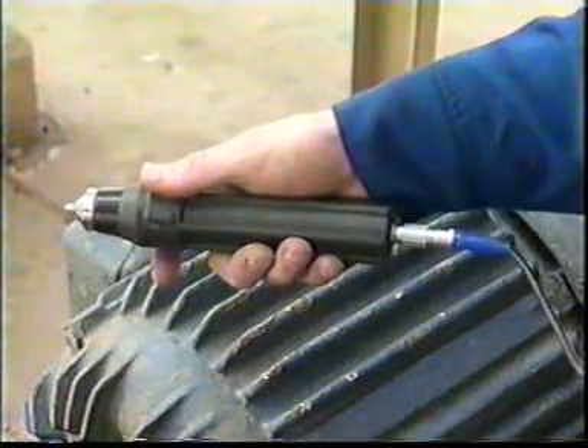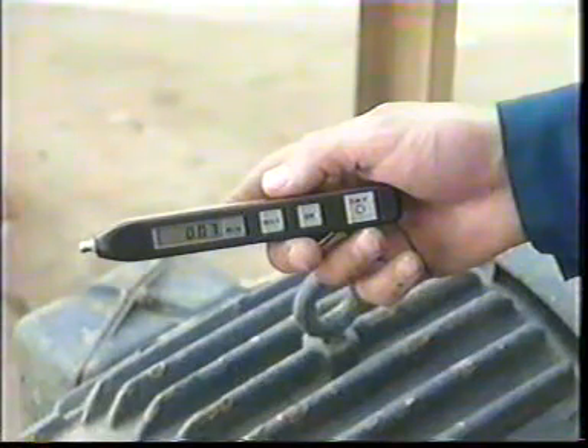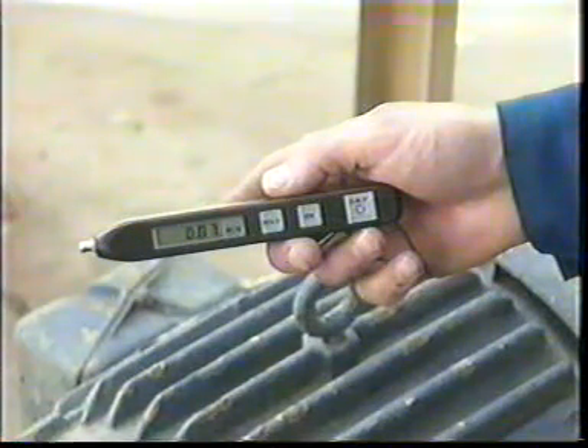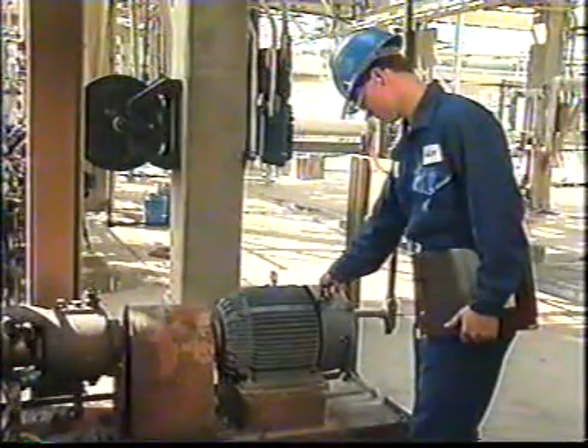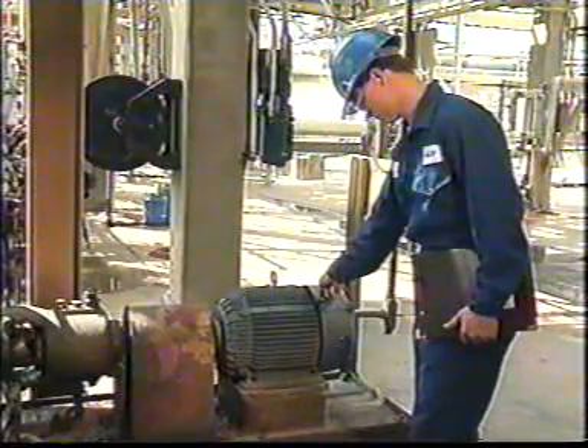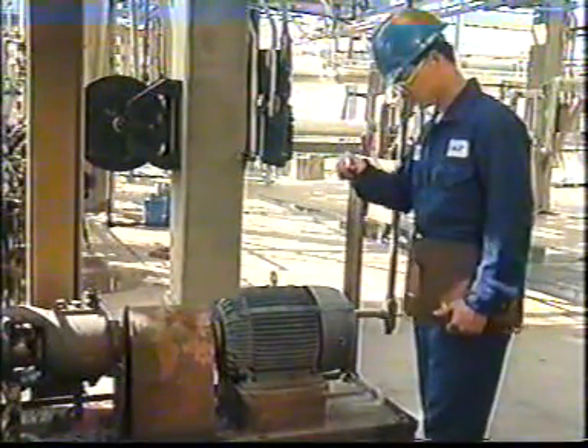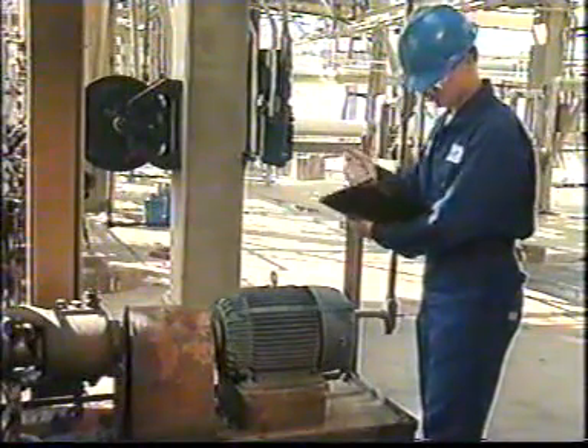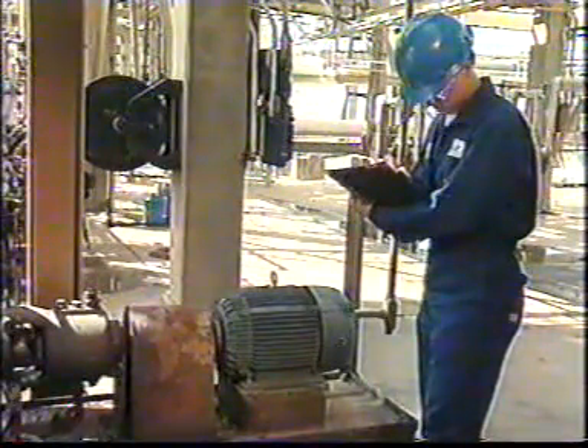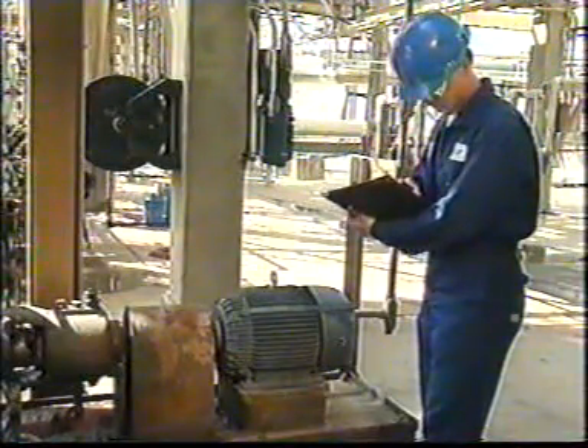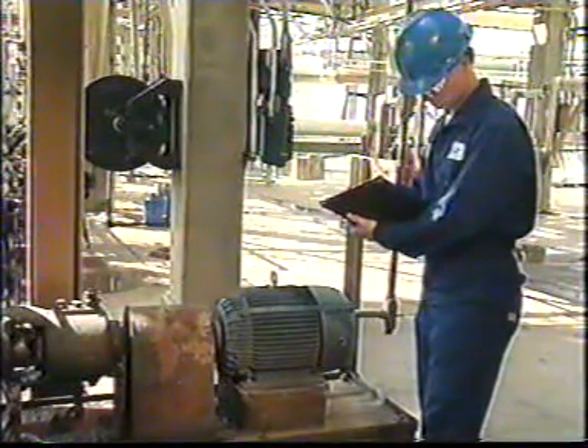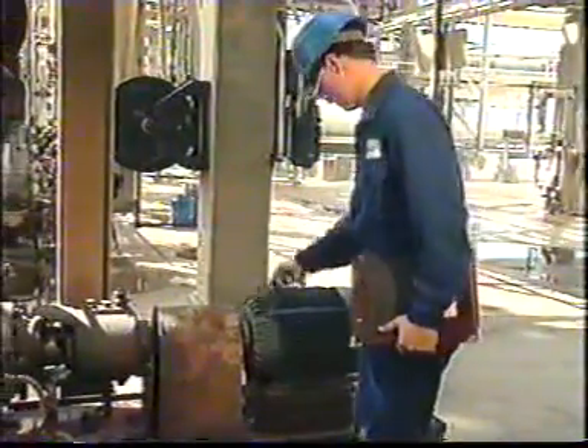Handheld probes are the easiest sensors to use. This probe is typically used for a quick look at machine condition and for measuring lower frequency ranges. Most probes provide a reading or display that the technician can assess or interpret on the spot. These devices are often battery-powered and have an accelerometer pickup. The handheld meter is durable and easy to use. The technician can walk a pre-planned route and take vibration readings in a relatively short time. Temporary mounted sensors are subject to a variety of errors that the technician can control.